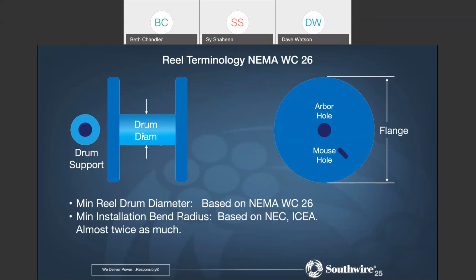If it's shielded, normally the OD times 12, which is your minimum bending radius. The point I'm making here is don't be misled that just because I sent it on a drum diameter that is smaller than what is allowed in the field as far as minimum bending radius, that's because of this. We go by NEMA, whether it's myself or our competitors, we all go by NEMA. NEMA tells us what size drum diameter you should use.